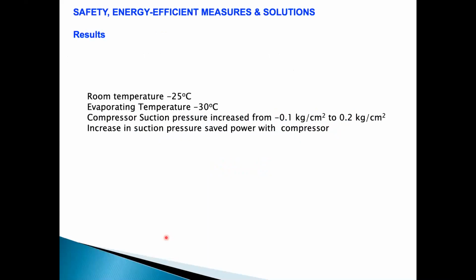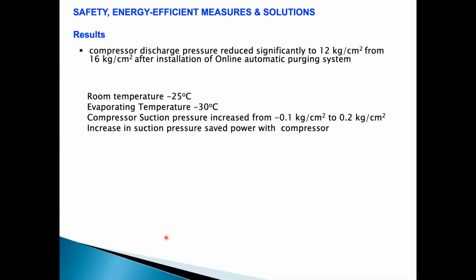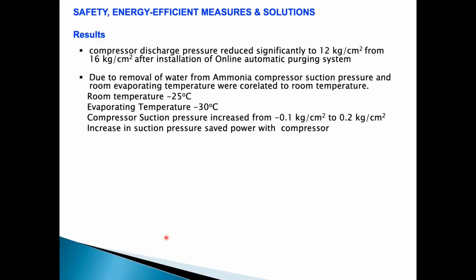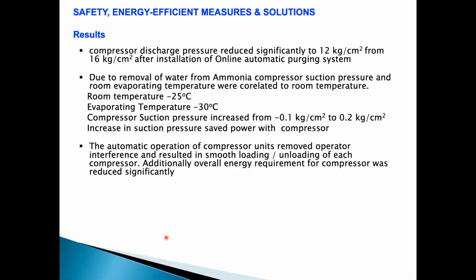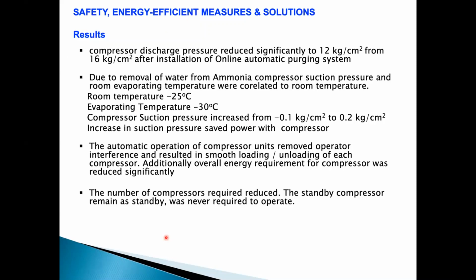So what we achieved: room temperature was minus 25 degrees. Evaporating temperature increased from minus 35 to minus 30 degrees centigrade. Suction pressure increased from minus 0.1 to plus 0.2 kg per centimeter square. Discharge pressure reduced to 12 kg from 16 kg. The compressor automation removed the need for the operator to interfere. Compressor loading, unloading and on-off operation was done automatically, and the overall requirement of compressor running reduced.